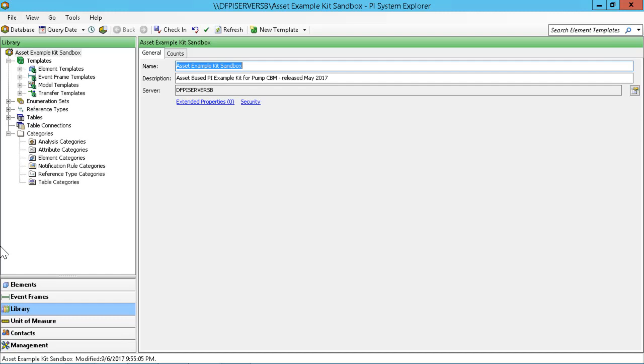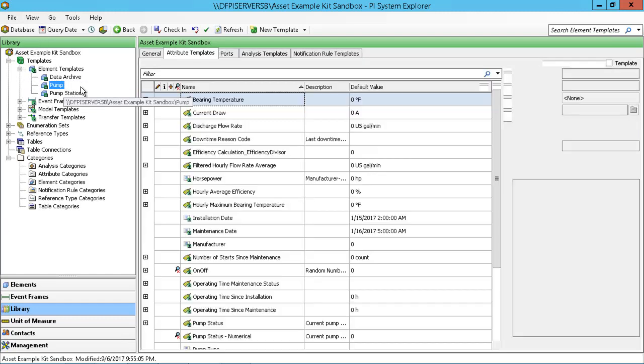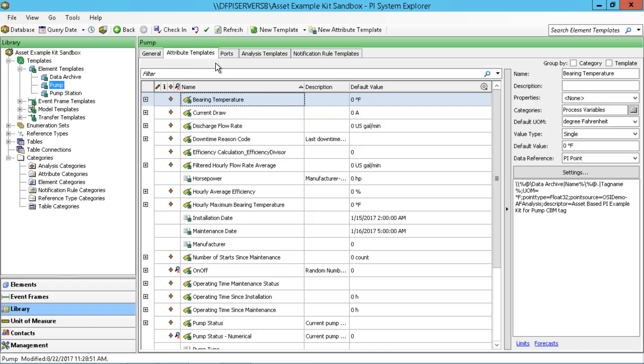What we want to do is add a dynamic URL to the individual pumps, and we can do that by using the URI data reference within PI AF. We're going to add this data reference as an attribute to our pump template. Browse to your pump template or whatever template you're working with — you can still add an attribute that will point to a display of your choosing by going through this procedure.